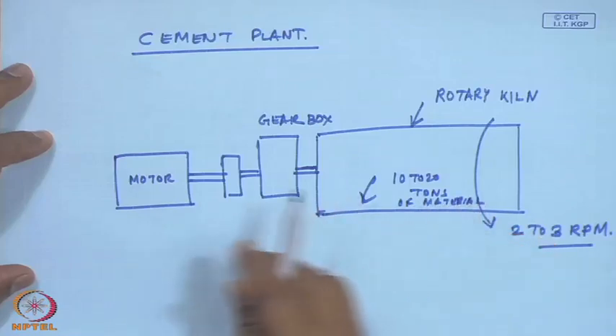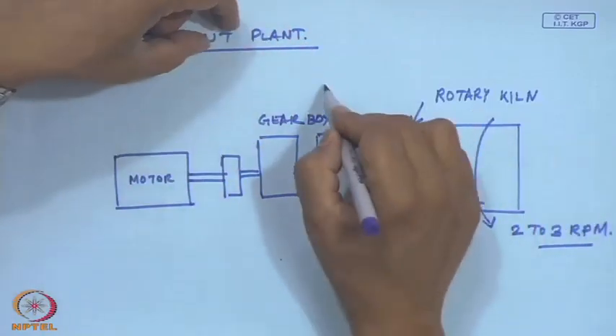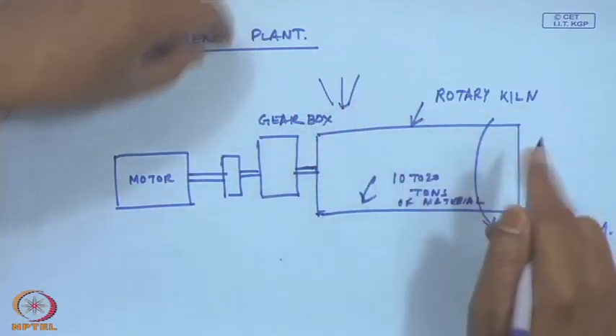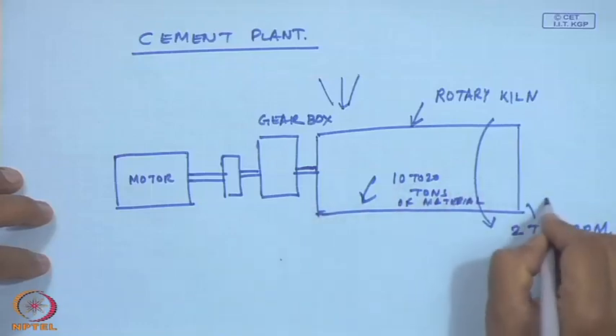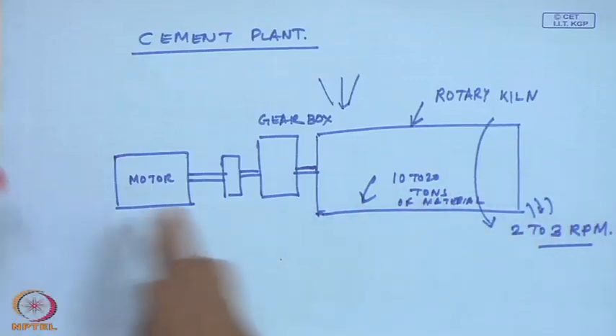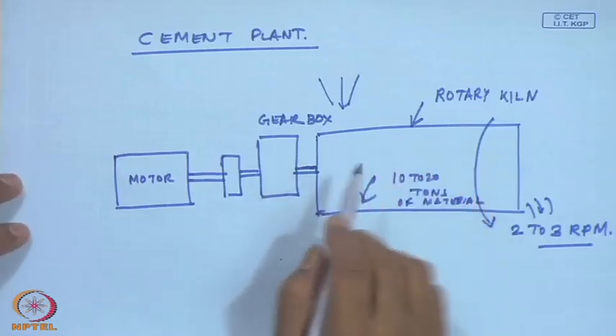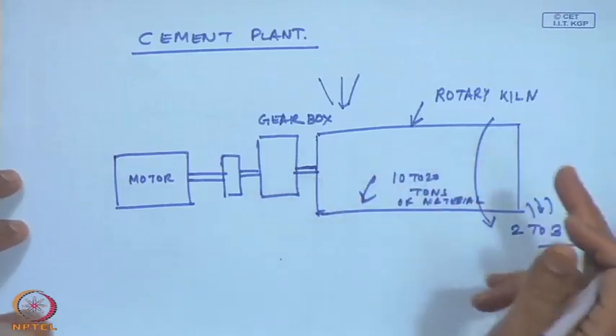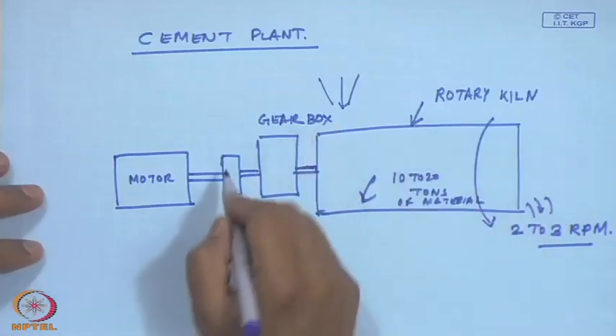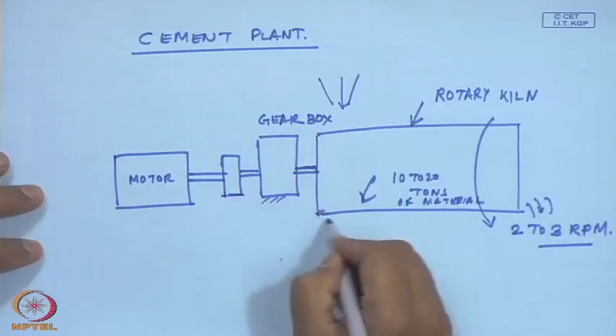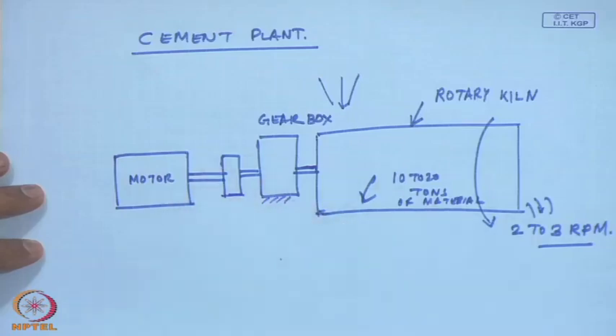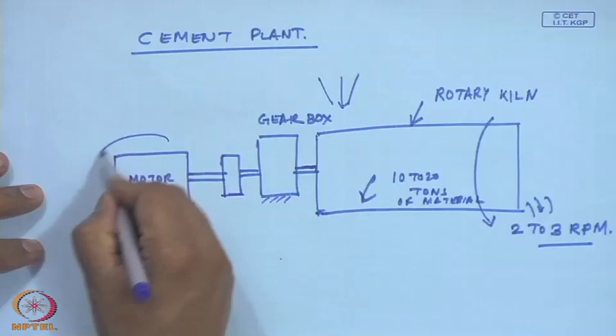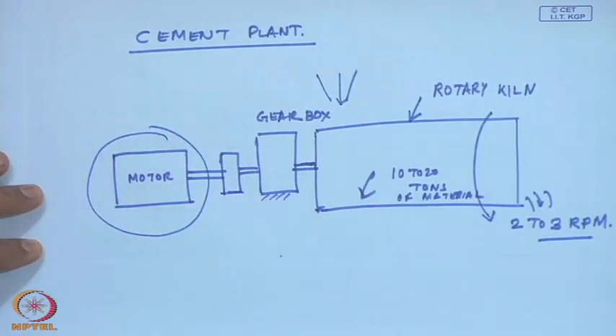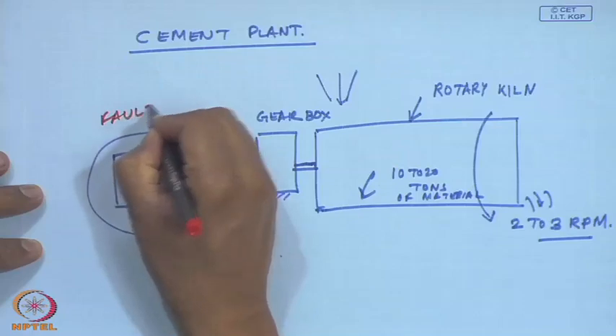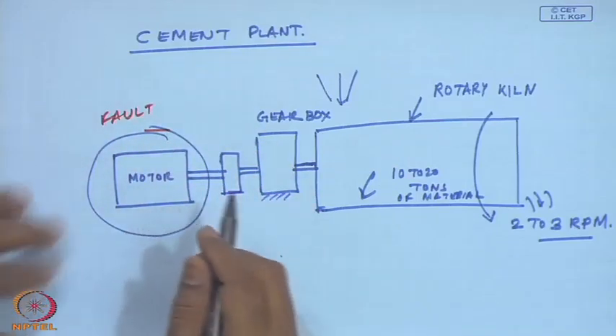The idea, as you know, in a cement plant, is that all the mix is added. There is a feeding device here, and then it is turned with a hard grinding media, and then you will have the powder cement coming out. But our focus is, we know how to find out the faults, the cracks in the kiln, which is a common type of failure in kilns. Failures in the gearboxes or the couplings are known to us through vibration monitoring, we can do that. But my focus here is on what happens if this motor is at fault. How do you find out a fault condition in the motor? Because if the motor shuts down, your plant is shut, isn't it?